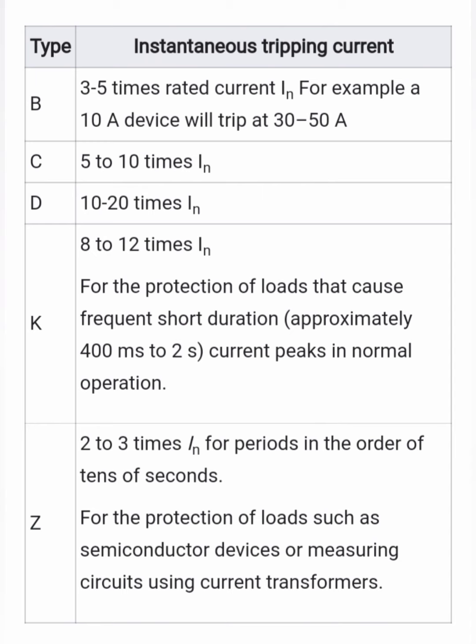Here, the instantaneous tripping current means how much load the MCB can withstand whenever a fault current or load is higher than the rated value. In a B type, 3 to 5 times the rated overcurrent will be withstood.